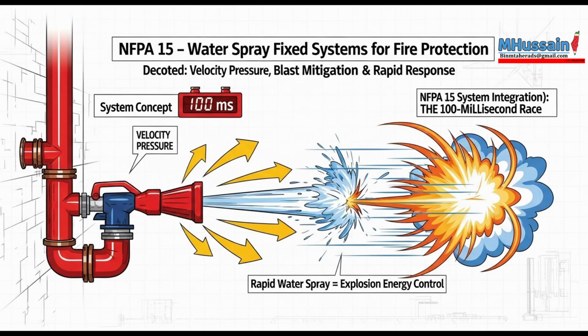Start with system volume, 12.3.4. The capacity controlled by a single actuation valve has to be kept small, limited to 500 gallons. Why so small? Speed is inversely proportional to volume. It's basic physics, really. Annex A.12.3.4 explains that the time it takes to pressurize the pipes and fill them with water is a huge chunk of that total response time. Inertia. Inertia, exactly. The smaller the volume of pipework, the faster the water column can accelerate and reach that most remote nozzle. Trying to push, say, 5,000 gallons through a big network in 100 milliseconds. Hydraulically impossible. Okay, makes sense.